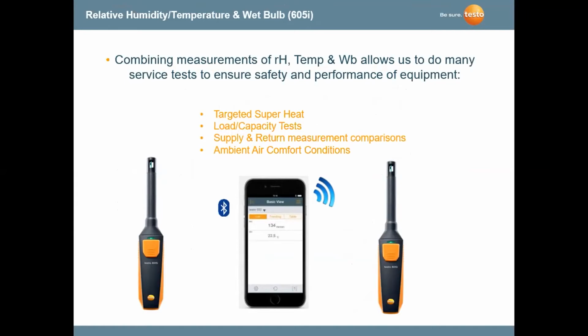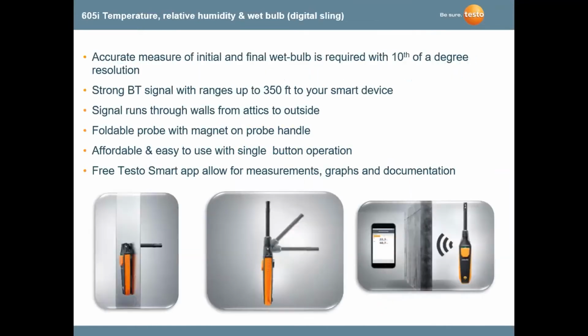You can see what you can do with this temperature relative humidity instrument, we call it a 605i. I call it a digital sling psychrometer, and it has no display. You're using your smart device to get the readings, and we'll go through that a little bit later when we start talking about the tools. These have a range of around 300 to 350 feet away from the cell phone itself, and you can set them up in different areas of the room and get your relative humidity, temperature, and wet bulb readings throughout the room. You can hook up 7 or 8 of these probes to one cell phone, depending on the type of cell phone you have.